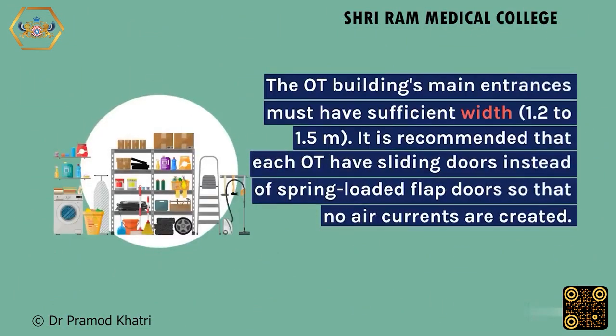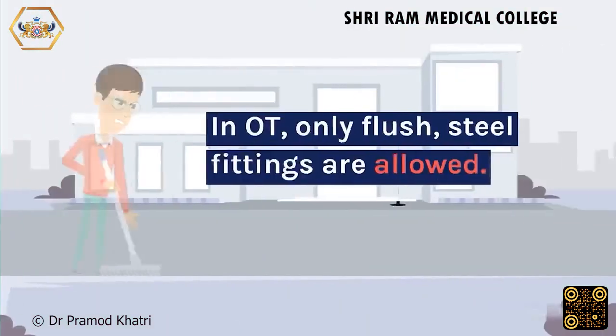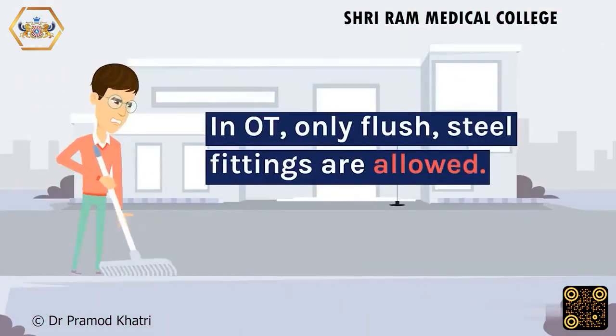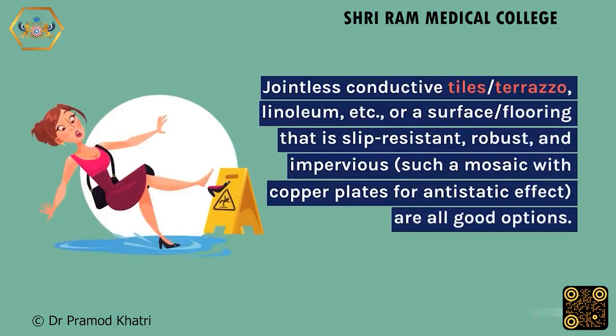The OT building's main entrances must have sufficient width, 1.2 to 1.5 meters. It is recommended that each OT have sliding doors instead of spring-loaded flap doors so that no air currents are created. In OT, only flush, steel fittings are allowed. Jointless conductive tiles, terrazzo, linoleum, etc., or a surface or flooring that is slip-resistant, robust, and impervious, such as mosaic with copper plates for anti-static effect, are all good options.